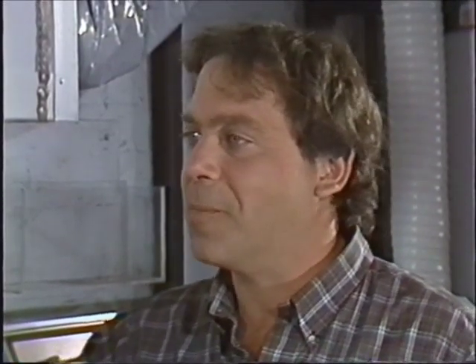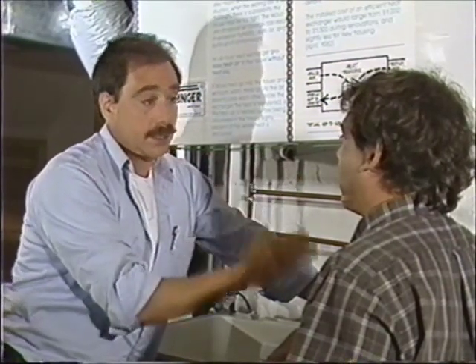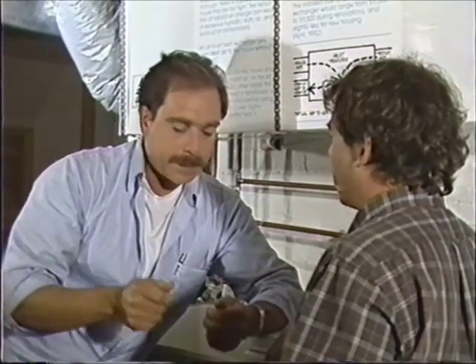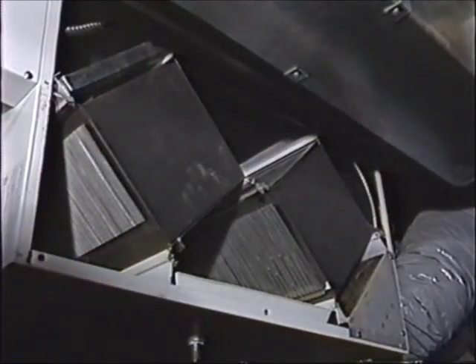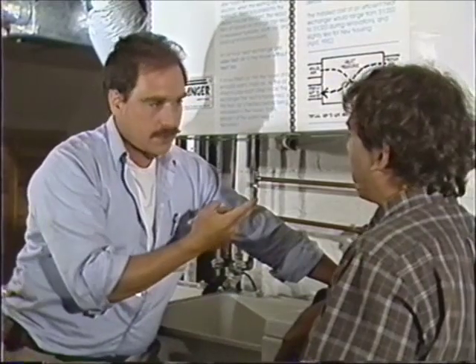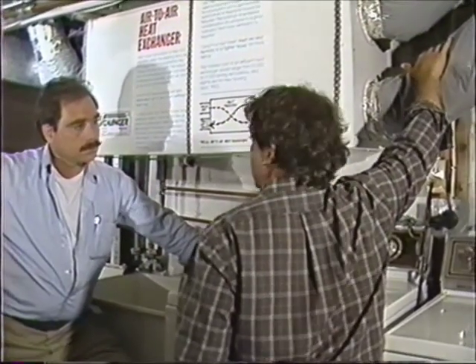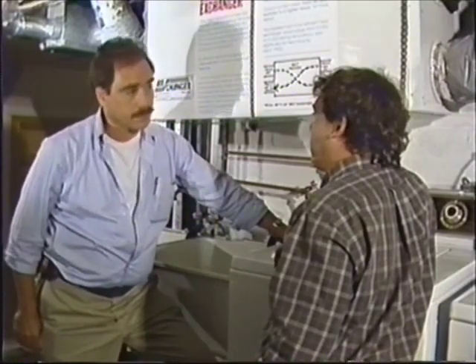You've written 'heat transfer' on the diagram — what's in the box? The strategy used by various manufacturers of heat exchange equipment changes a little bit. In this particular case, and in many other units, what we have is a sheet of polypropylene — it comes like a piece of cardboard, and there are a number of these sheets spaced apart. If you looked inside, each sheet is like corrugated cardboard, so you can pass one air stream through the sheets themselves and the other air stream in between the sheets. Because the surface area is so large, it's possible to exchange the heat very easily. The flexible ducts take the shortest route to outside.